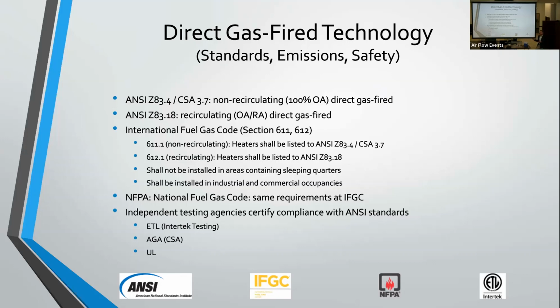These standards are set in place to ensure the safe and proper operation of these direct fired burners. It's also important to note that your international and national fuel and gas codes require any direct fired product installed on a building to be third party listed to be in compliance with those standards, to make sure that they're being applied in a safe manner.